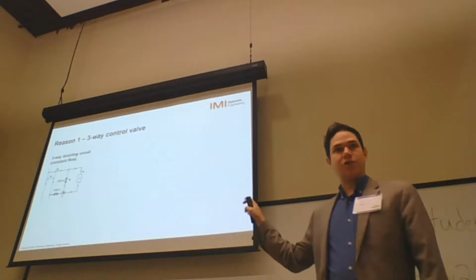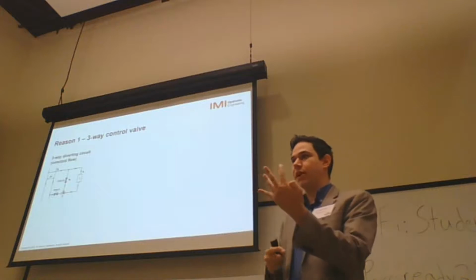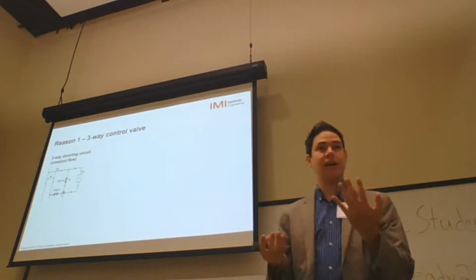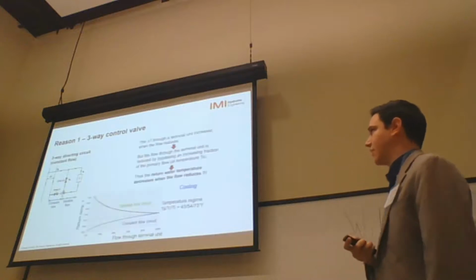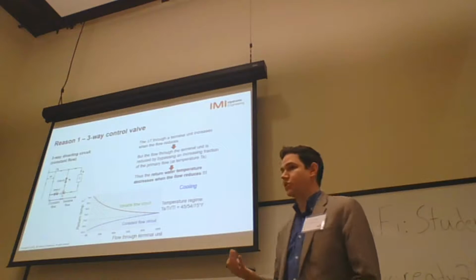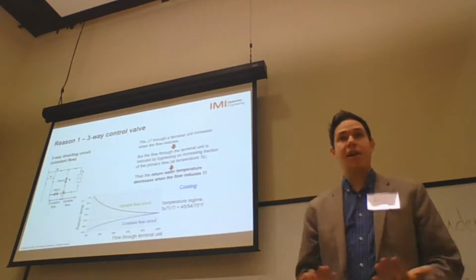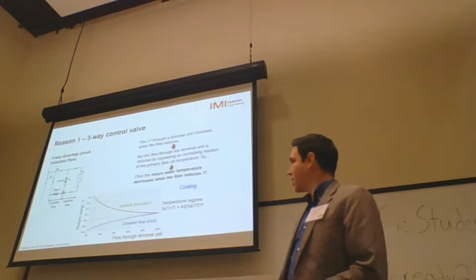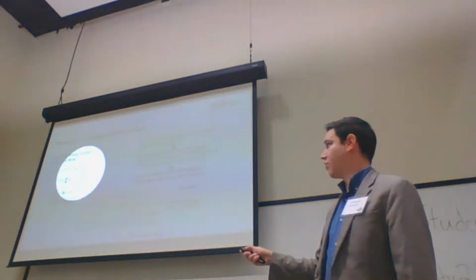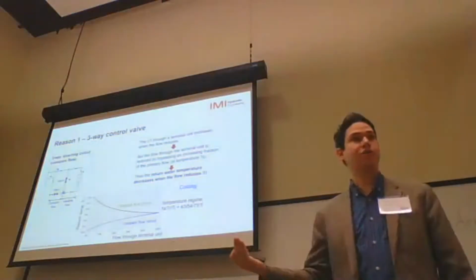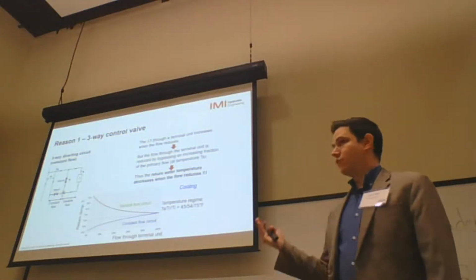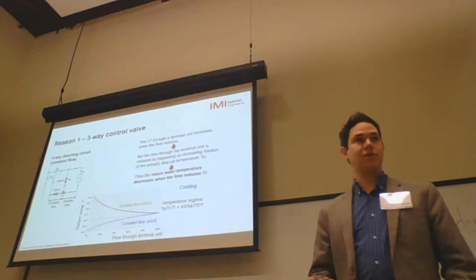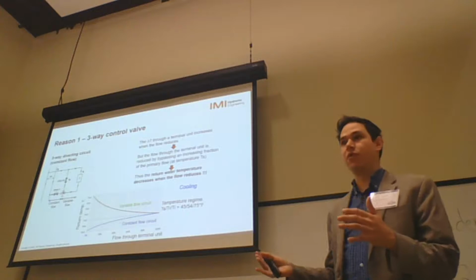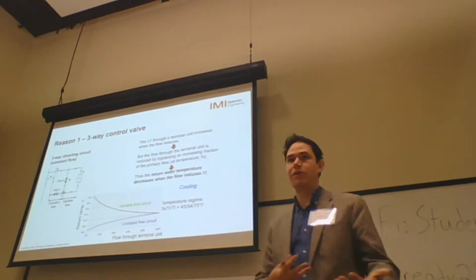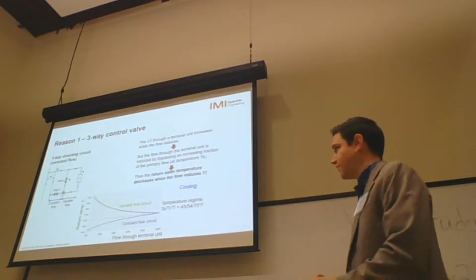The reason that I like to make this quick intro is to show the 4 reasons and how to tackle or how to solve that in a job site, or how to solve that in a real life example. So the reason number 1 is nothing that we can do in the job site depending on the installation. If we do have the 3-way control valves in the system, if you're not using the coil, so you have no heat transfer, all the water coming here goes back to the chiller, or goes back to the chiller plant. So if it's a 45 supply, the return would also be 45 degrees. So nothing much that you can do if all of the control valves are three-way control valves. You're going to have the low delta T issue and waste a lot of energy on the chiller consumption.